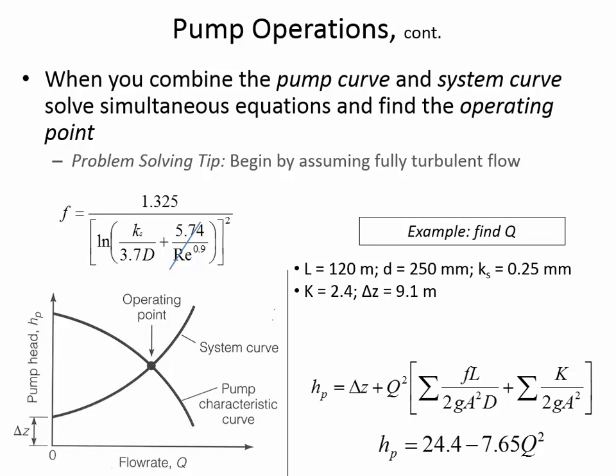Okay, so here's our friction term. We also need to have the local losses term. 2.4 is the K value divided by 2G times the area squared. So 0.04909 meters squared, square it. I'm going to write down some intermediate steps here just so I can double check my calculations. This is 198.98. Here is 50.76. And doing this is useful also just to look at the relative importance of the minor losses or local losses compared to the frictional losses. And it's about 4 to 1. The frictional losses are 4 times greater here than the local losses.